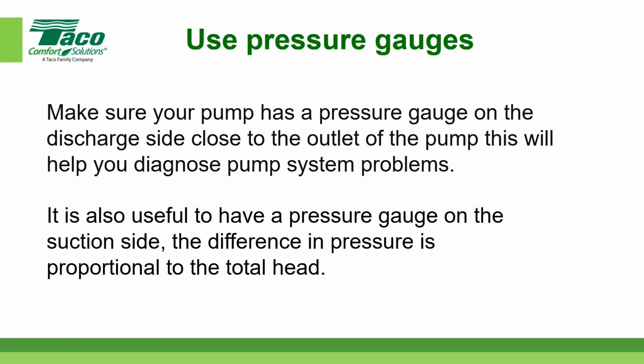So can you replace the gauge with a compound gauge that reads both positive pressure and either negative pressure or inches of mercury? And sure enough, they put the compound gauge on. It was reading 20 inches of mercury on the negative side. So my recommendation is that if it's a condenser water system, not only put a gauge on the suction side, but make sure it's a compound gauge.